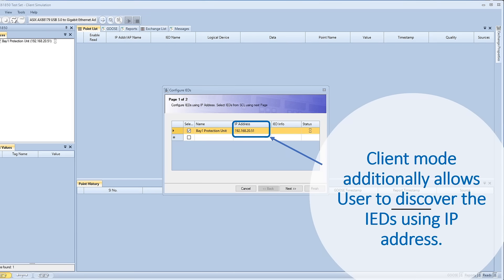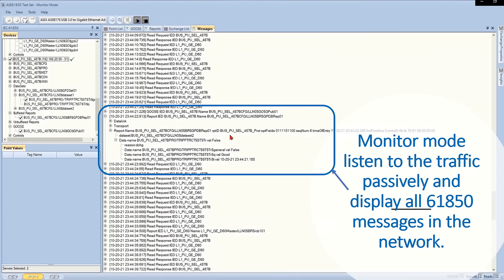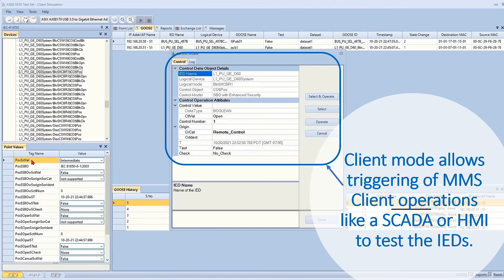Server mode simulates IED functionality with MMS and GOOSE features to test other IEDs or HMI in the network. Monitor mode listens to the traffic passively and displays all IEC 61850 messages in the network.